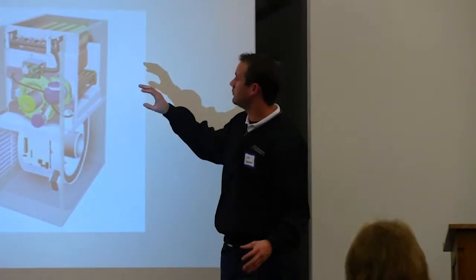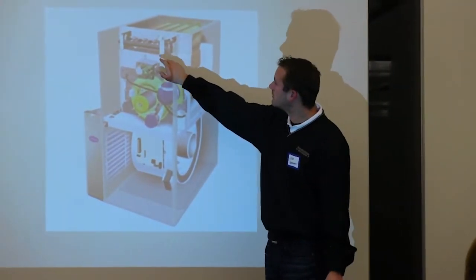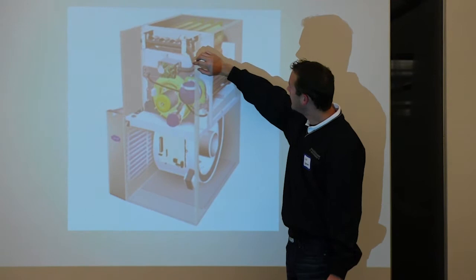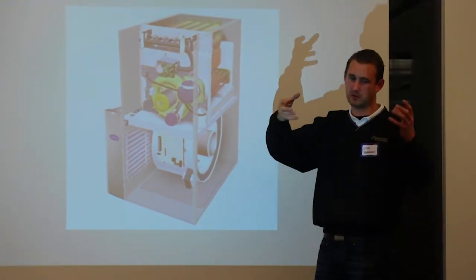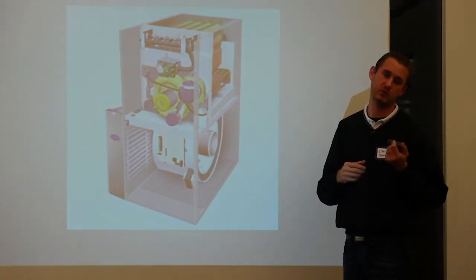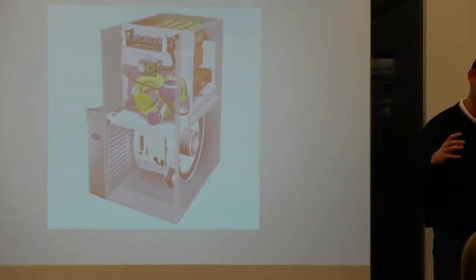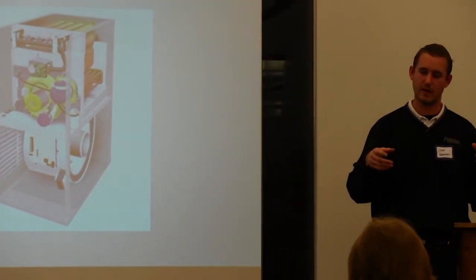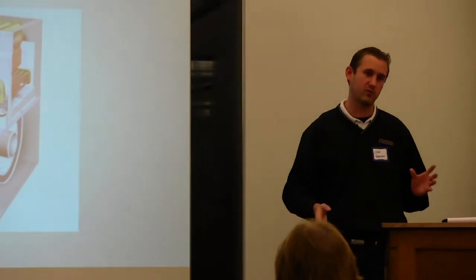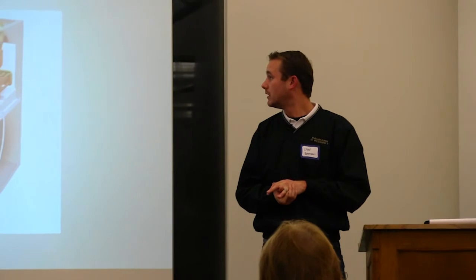So the final thing is a visual inspection of the heat exchanger. I'm sure everybody's heard the horror stories of heat exchanger cracks and everything like that. What a heat exchanger is, it's a sealed metal tube essentially. So after the flames kick in on the burners, it travels through a series of tubes, and basically there's a lot of bends through these tubes. You're basically trying to trap this heat in this sealed container as long as you can, so that as the air is moving past the sealed container, the air is picking up that heat.